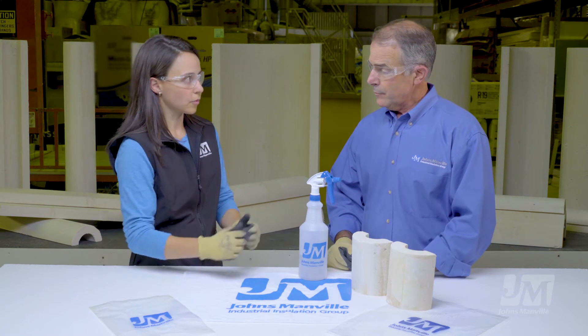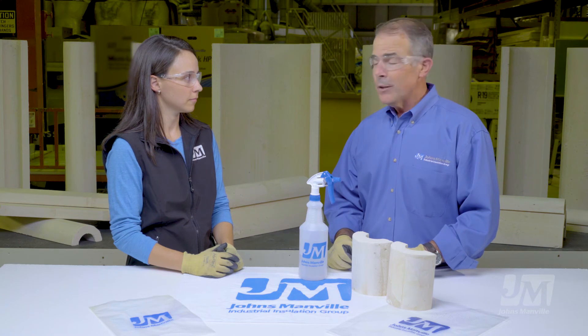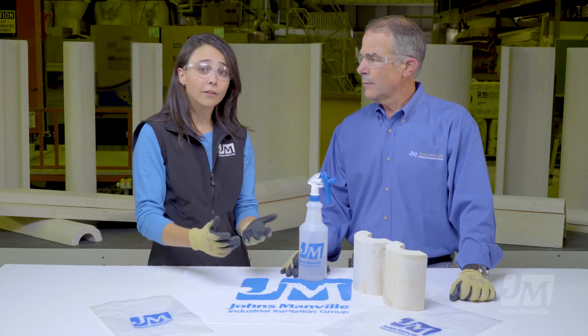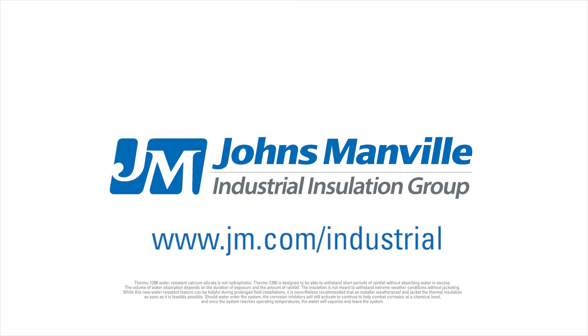These two products look pretty similar. If I'm on a job site, how am I going to be able to tell them apart? They look the same, actually — it's pretty hard to tell the difference. The only way, if it's out of the box, is to spray some water on it and see if it beads up and runs off or not. That's the only way. Obviously this is a huge evolution for calcium silicate insulation. If you'd like to know more about Thermo-1200, please visit our website at jm.com/industrial, or contact one of your regional technical managers.